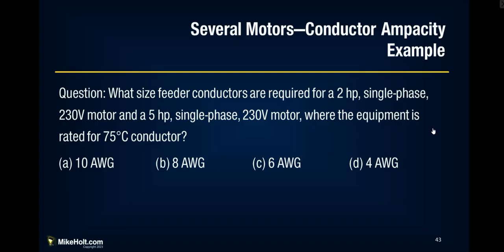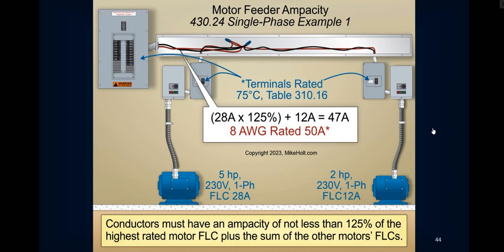What size feeder conductors are required for a 2 horsepower single-phase 230 volt motor and a 5 horsepower single-phase 230 volt motor where the equipment is rated for 75 degrees Celsius conductors? So here again, we're taking the calculation because we have a 5 horsepower motor that has 28 amps times 125% plus the 12 amps that's for the other motor. That gives you 47 amps.